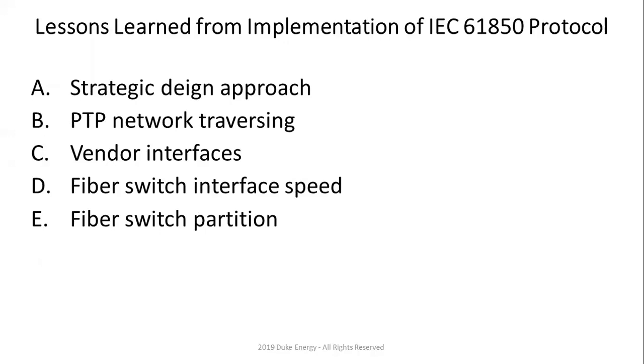So when you get to the switch, the first thing you do is partition, right? You can take two switches or you can take one switch and partition, it doesn't matter. You have to create two buses, right? One is a process bus, one is a station bus. This is for your sample values and for your GOOSE messaging, right? Well, if you create a bus for your sample values, and say you have 30 sample values coming from the field, and you have about 4 or 5 relays in the back.